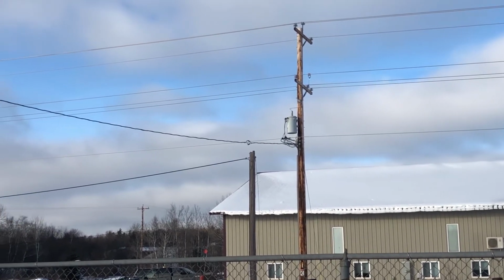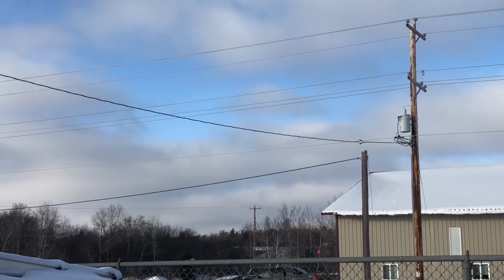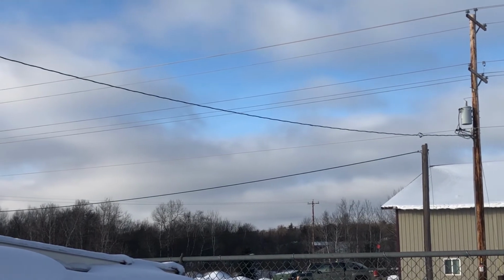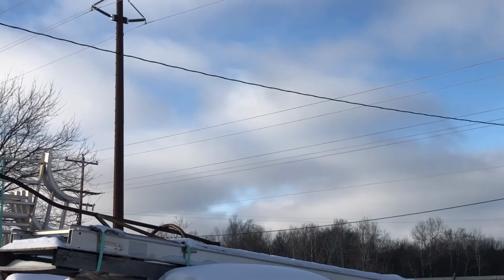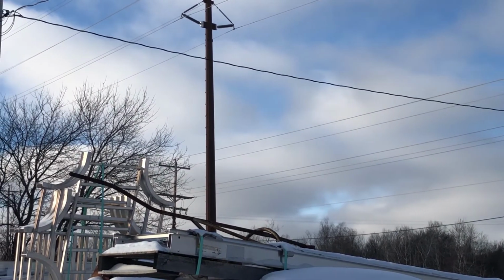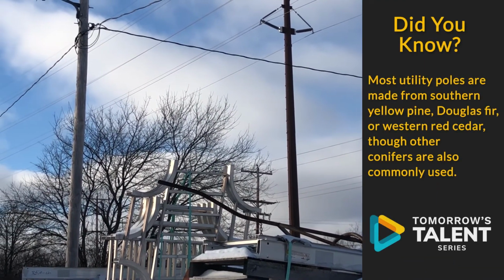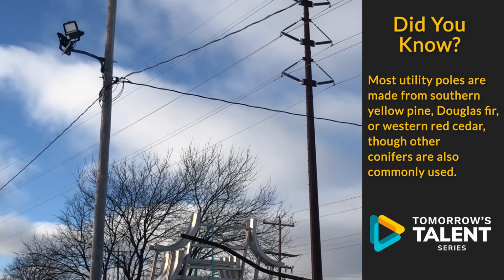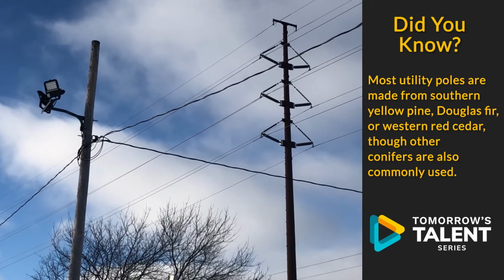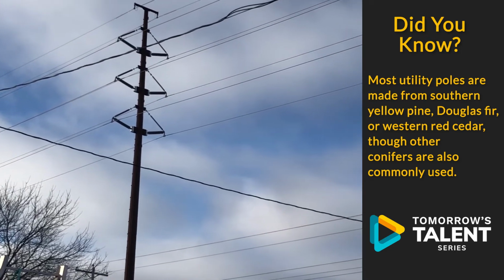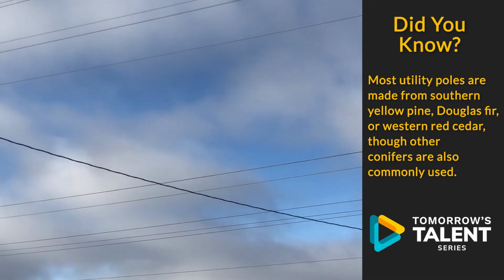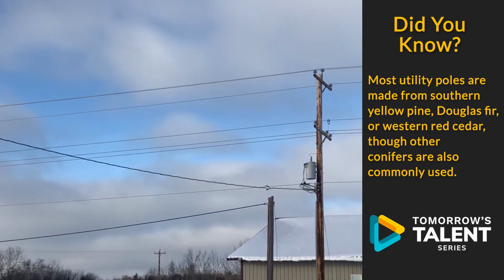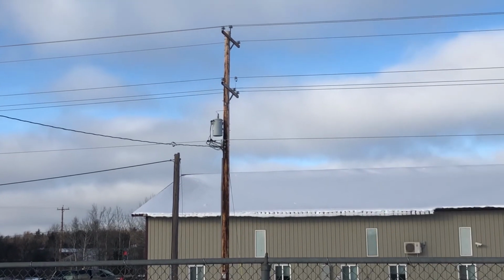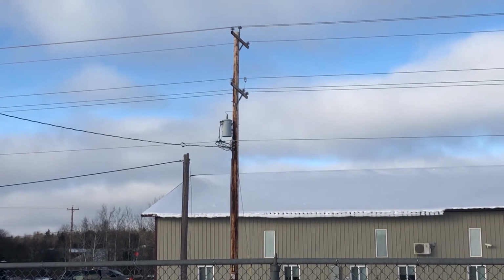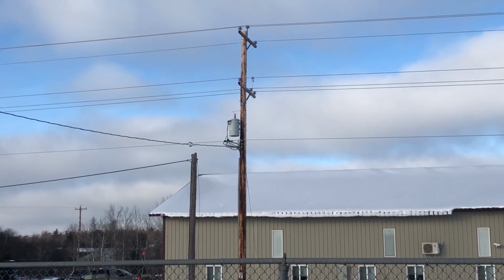So this is an example of a distribution circuit that we're feeding a business, and in this one, as an engineer, you basically figure out where this transformer is going to go in the system, what size cable is going to be on the distribution circuit, how big a wire and how much current is going to be drawn, and then even down to the design of the pole, the specification on it. You know, what type of pole material you're going to use. Is it pine or cedar or other materials? So as an engineer, you basically decide what's going to be in that pole itself.